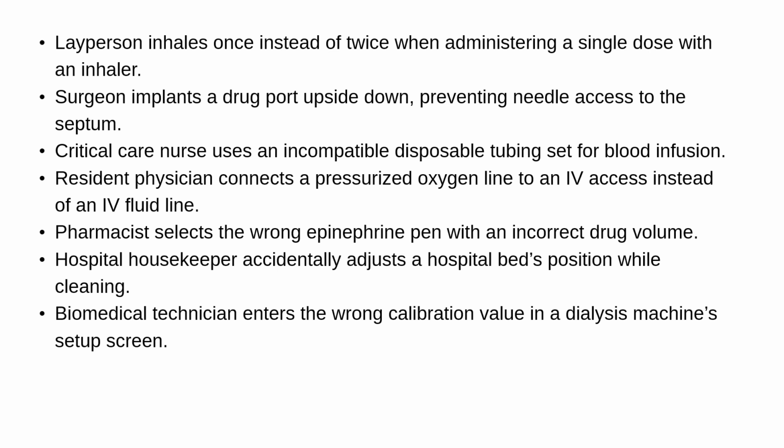A pharmacist selecting the wrong epinephrine pen with an incorrect drug volume. Mistake. A hospital housekeeper accidentally adjusts the hospital bed position while cleaning. While they bend down unintentionally, if they keep their hand on one of the levers, it could change the position of the bed. That could create some discomfort to the patient. Then a biomedical technician enters the wrong calibration value in a dialysis machine setup screen. See, all these are mistakes. But if you look with an engineer's perspective, you can understand that this can be brought down by proper design. Right.